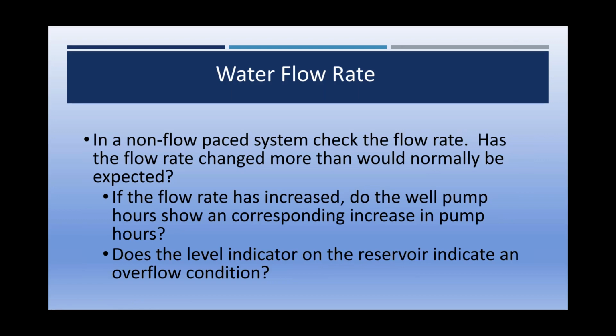I've had people basically have issues with their controls. Often in some reservoirs, you'll have float controls that just turn on the pump and turn it off depending on the level in the reservoir. And when that failed, the operator decided he would just turn his pump on 24/7 and let the water fill up the reservoir and then overflow. Okay, not the best solution to that problem.